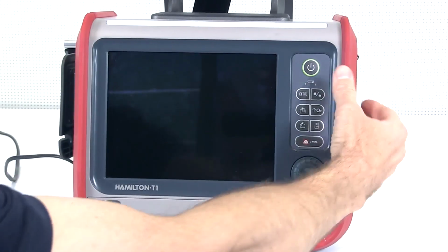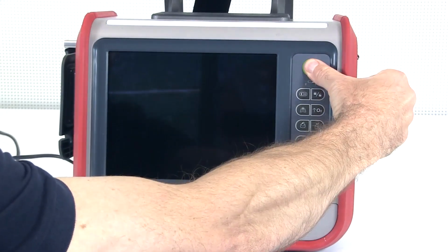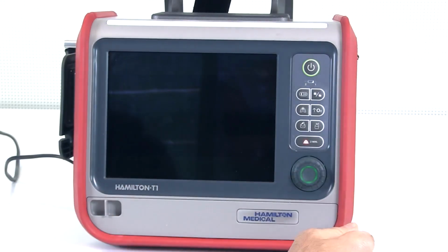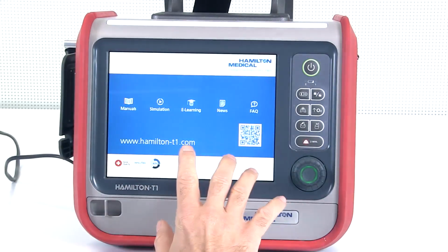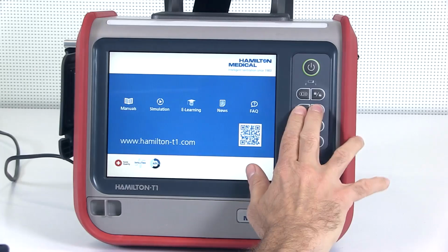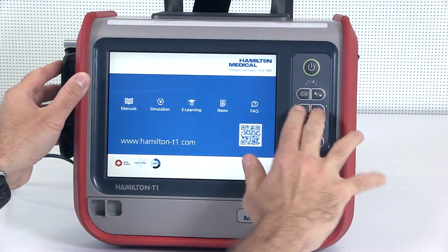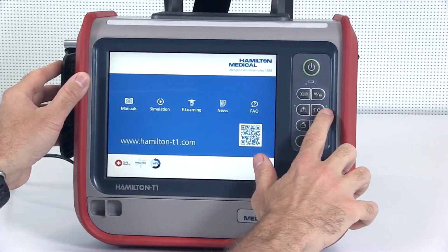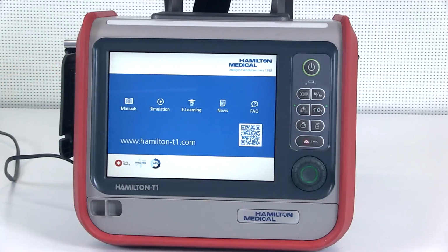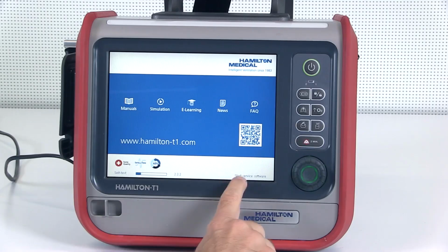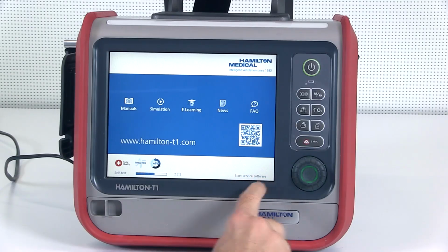Turn on the ventilator unit by pressing the power button. Then press the O2 enrichment and manual breath keys at the same time until the two corresponding green LEDs light up. The bar indicates the progress of the startup self-test procedure. The startup status of the ventilator service software is shown in the bottom right corner of the display.